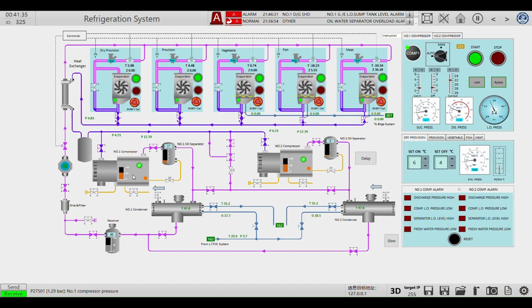So there is a line basically from this lube oil line. One line goes towards a pin; there is a sleeve, and above the sleeve there is a pin. So the lube oil will go and the pin will lift up. When the pin lifts up, it opens the suction valve, due to which there is no compression. And this lube oil, which lifts the sleeve up, is controlled by a solenoid valve, and that solenoid valve is controlled by the suction pressure, which we see, and that's how capacity control is done.